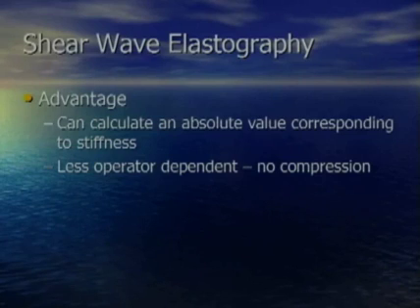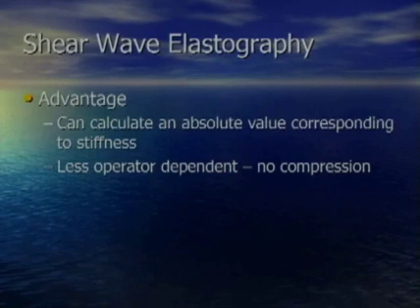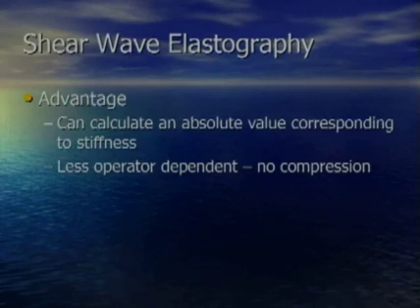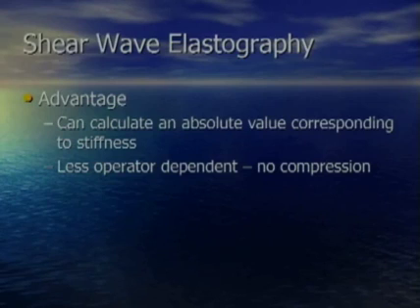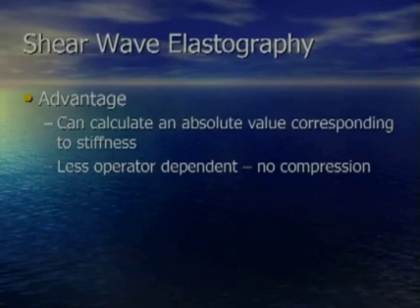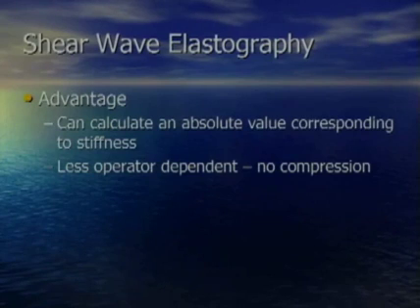Regarding shear wave elastography — this is a quantitative measurement. We put an ultrasound push pulse into the tissue and generate a shear wave, similar to throwing a pebble into a pond and generating waves from the entry point. Measuring those waves as they propagate through tissue tells us how hard or soft something is. This technique is less operator-dependent because we don't have to worry about displacing tissue by compression — though pre-compression does still play some role, so you should still apply very little pre-compression when acquiring the image.